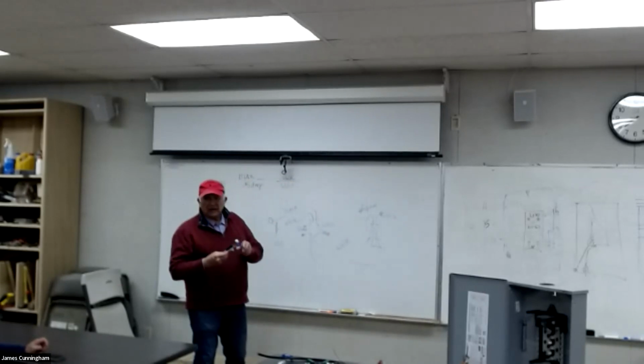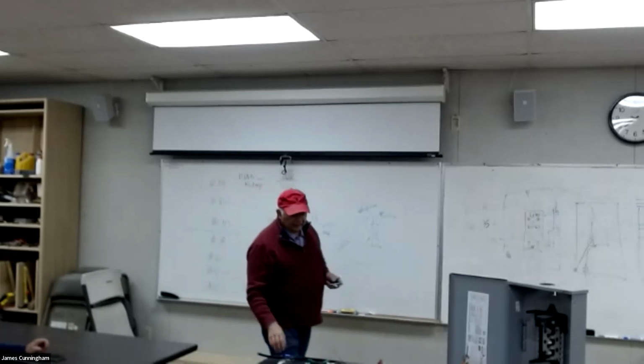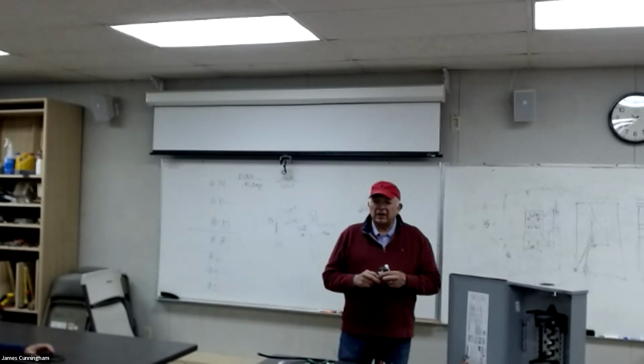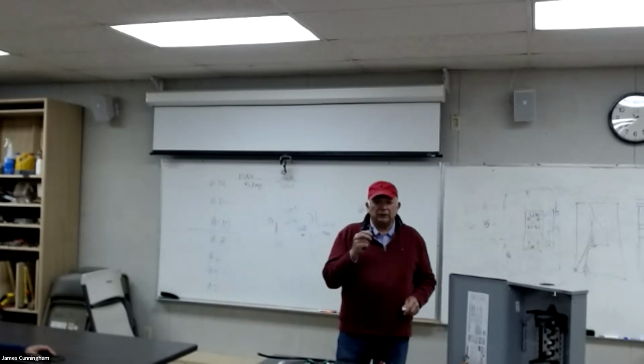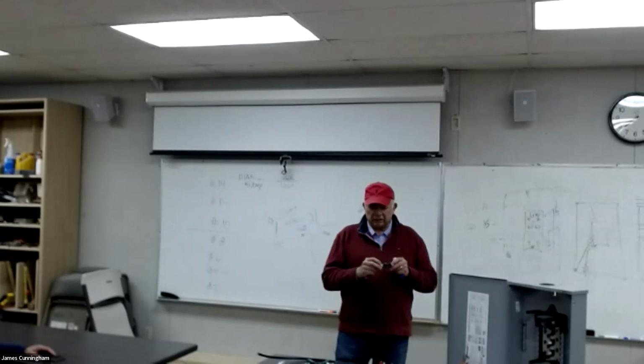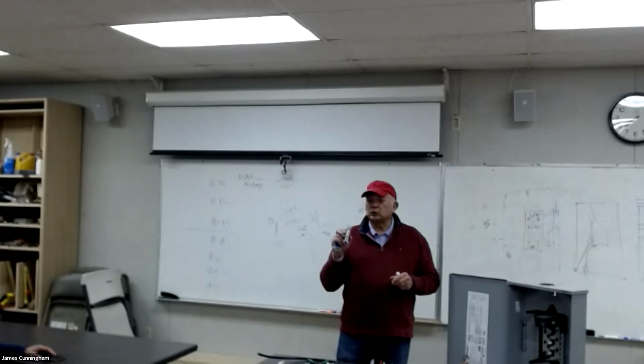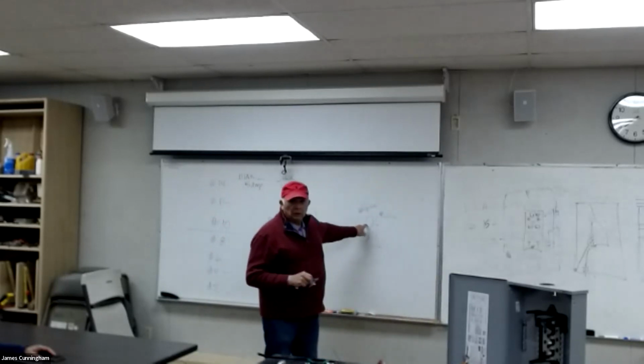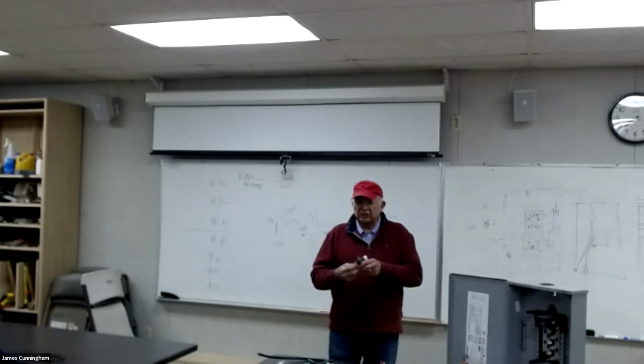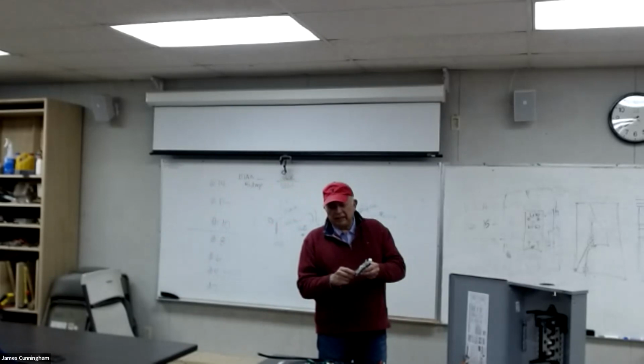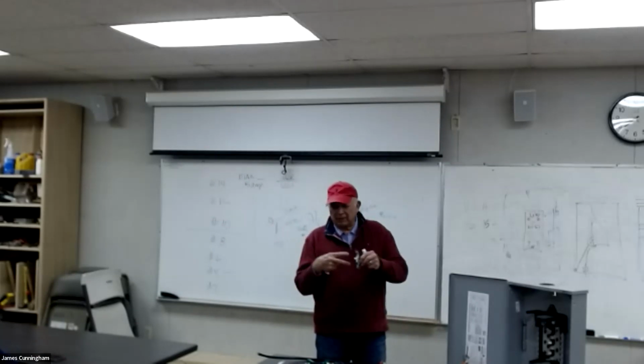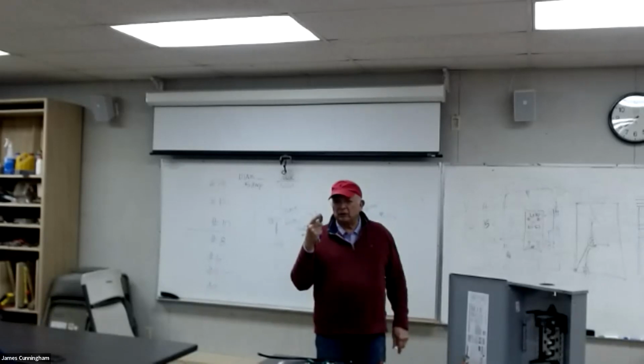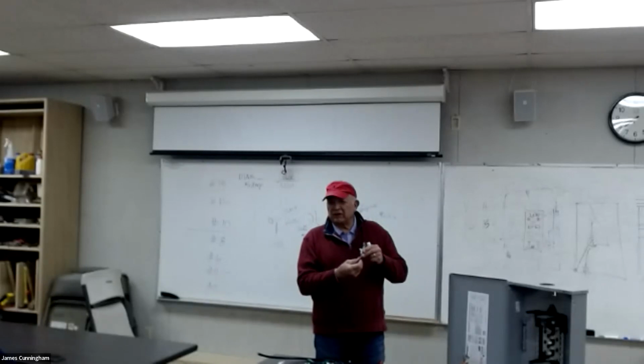The switches do have a ground screw. The electrical code allows me, if I'm putting this in a metal box that's grounded, all metal boxes have to have a ground screw in them with a ground wire to it. If I'm putting this in a metal box, I don't have to connect the ground screw to a switch. The ground wire does have to go to the light fixture. But if it's a metal box, this is all metal, it's got a ground screw, it's got screws that screw it to the metal box, so you're actually getting grounding from the screws that hold this device to the metal box.